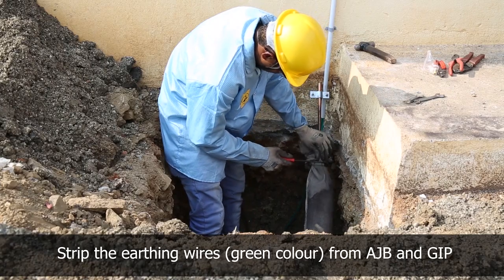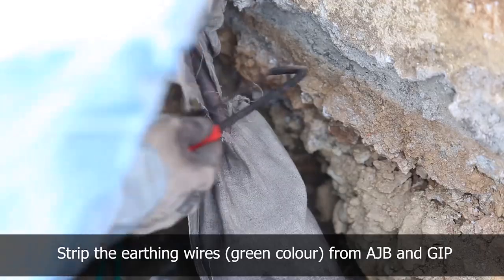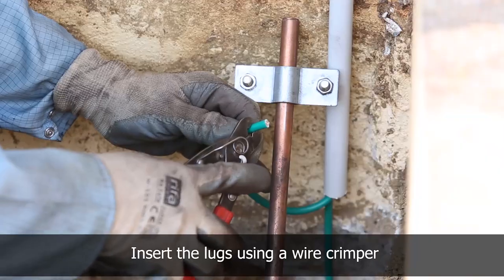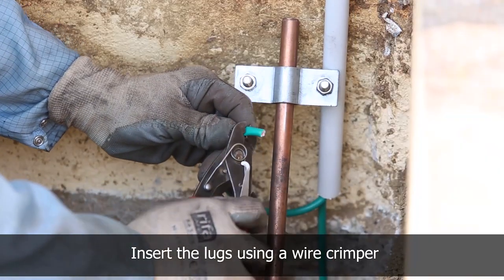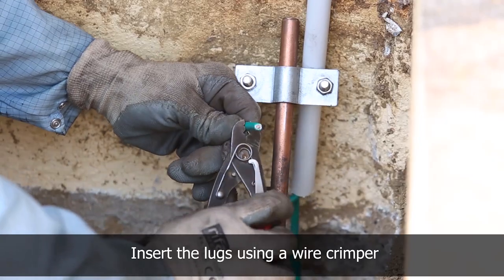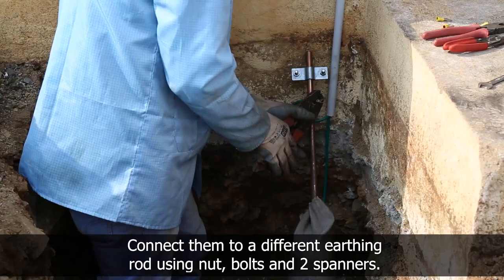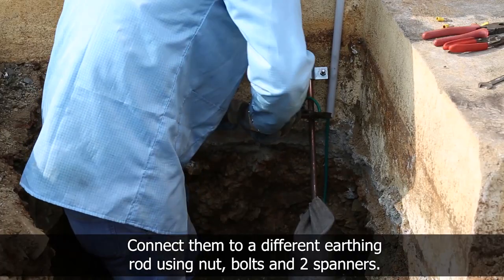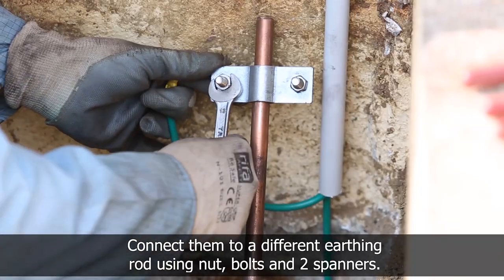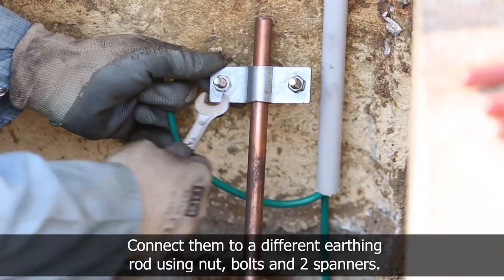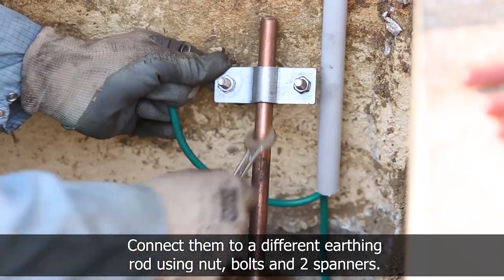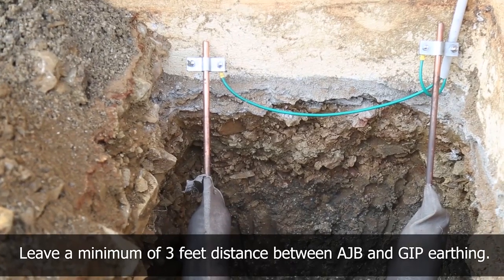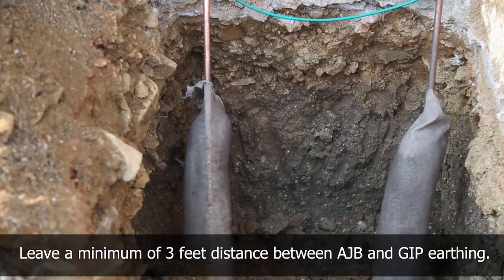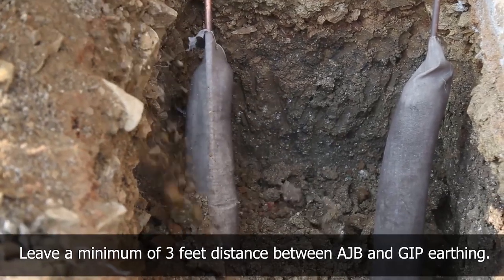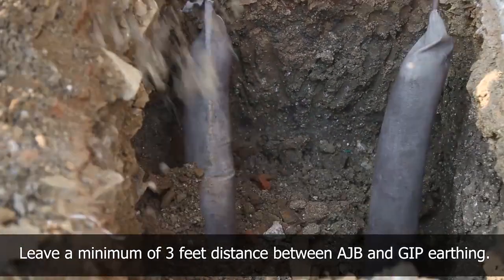Now, to do the earthing, dig two earthen pits of 1 foot by 1 foot by 3 foot and use the ready-made chemical earthing kit. Strip the earthing cable from the array junction box and the grid input protection box and connect it to the clamp of the earthing rod. Leave a minimum of 3 feet distance between the earthing of the array junction box and the grid input protection box and fill the pit with mud.